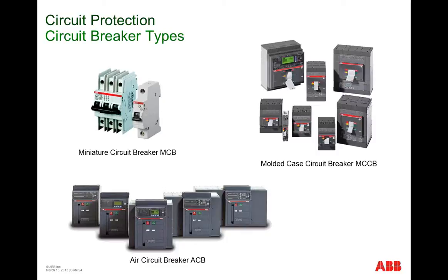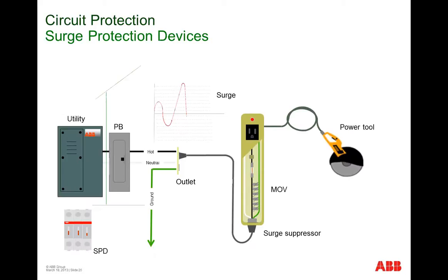Circuit breakers are found in 3 main types. A miniature circuit breaker, on the left here, is typically mounted on a steel rail within an electrical enclosure. A molded case circuit breaker is screwed onto a backplate in an enclosure, and that's shown in the upper right. And then finally, an air circuit breaker is found in higher current ranges, typically in incoming switchgear, and it's usually either rack-mounted or screw-mounted into the panel of basically a box of switchgear.